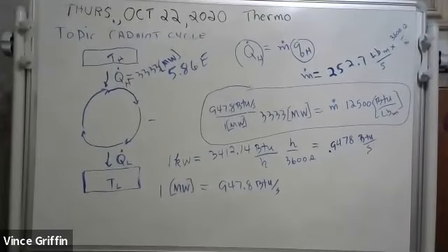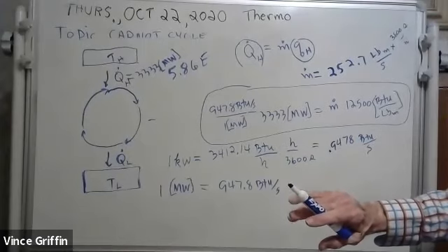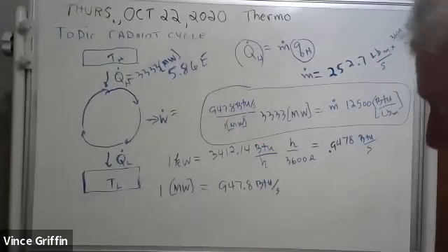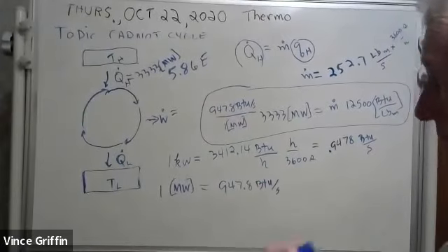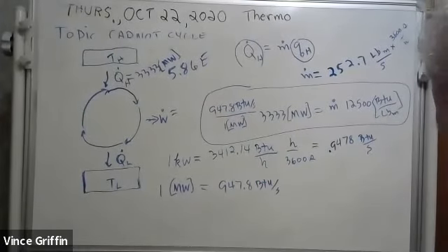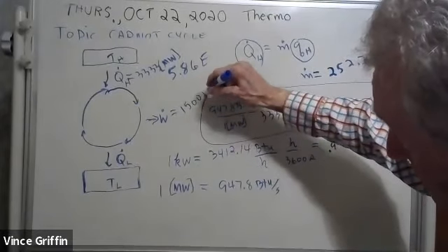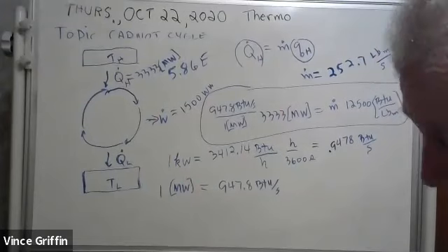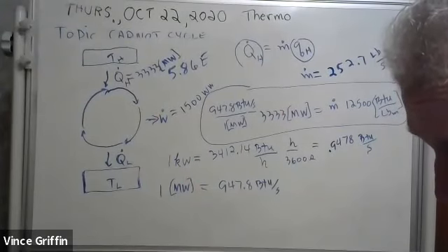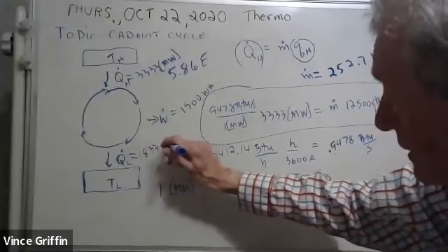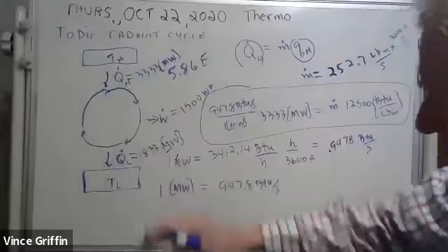Now, the heat rejection, what did they say? It's 45%. I had this a minute ago, and I think I erased it. It's 45% of that. So we take 3,333 times 45%. Let's just round it off to 1,500 megawatts. The heat rejection rate, you just subtract these, Mohammed. Subtract that from 3,333, and I'm getting 1,833 megawatts is your heat rejection. See, these have to add up to that.